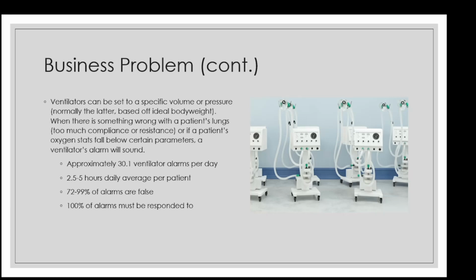Ventilators are designed with a variety of settings to customize performance for nearly every individual. But the question then becomes, how do we discern who needs to have their ventilator functions altered versus false alarms? The current answer to that question is to have a healthcare worker, typically a nurse or respiratory therapist, thoroughly examine the patient, ventilator, and all connections between the two every time a ventilator alarm sounds. This process normally only takes approximately 5 to 10 minutes per occurrence.